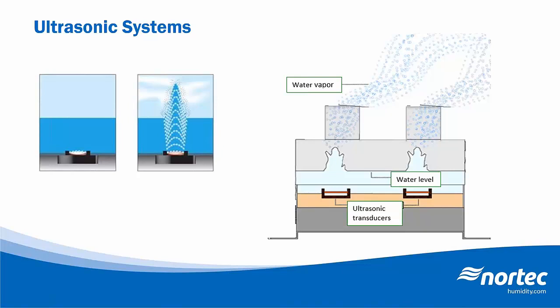Now, a design consideration for these types of systems is scalability. The ultrasonic units are typically smaller in capacity compared to the other types of systems, with outputs typically less than about 100 pounds per hour for a single unit, compared to, say, an evaporative media system or a nozzle system that can easily provide up to 2,000 pounds an hour from a single system. So for that reason, ultrasonic units are typically more cost-effective for smaller data centers. And in terms of energy consumption, a typical 40 pound an hour ultrasonic unit will consume just under 1 kilowatt of electricity, including a blower fan.